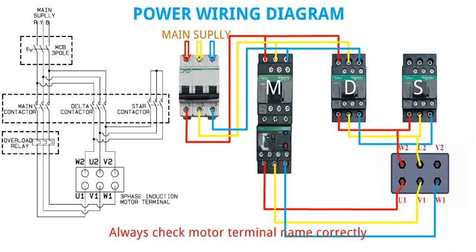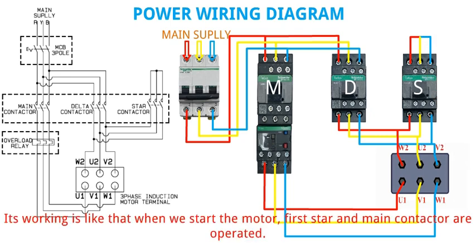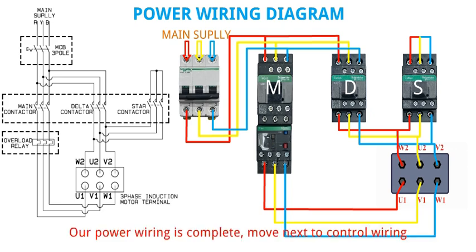Always check motor terminal name correctly. Connect the output of both star and delta contactor with motor terminal W2 U2 V2. In last, short the input terminal of star contactor. Its working is like that: when we start the motor, first star and main contactor are operated. After few seconds, star contactor turns off and delta contactor gets started. Our power wiring is complete.